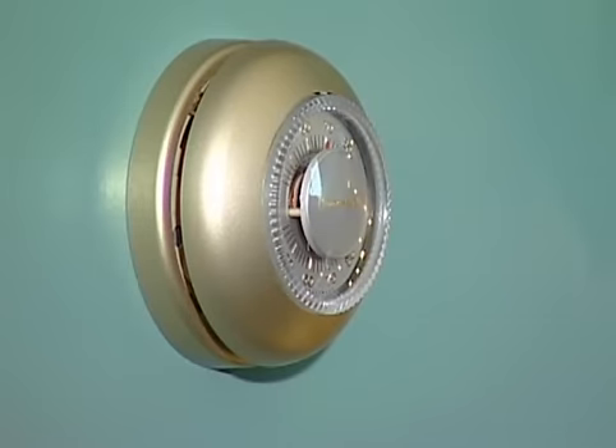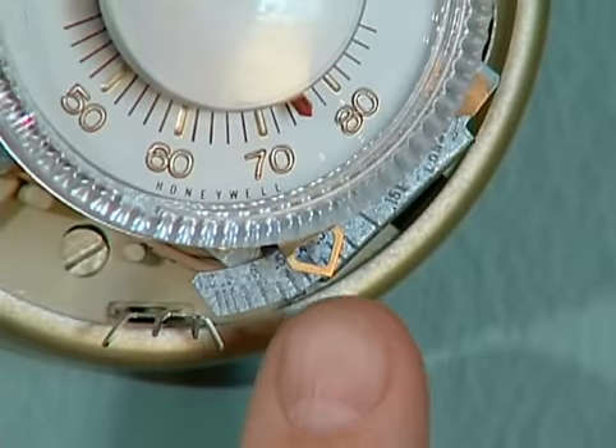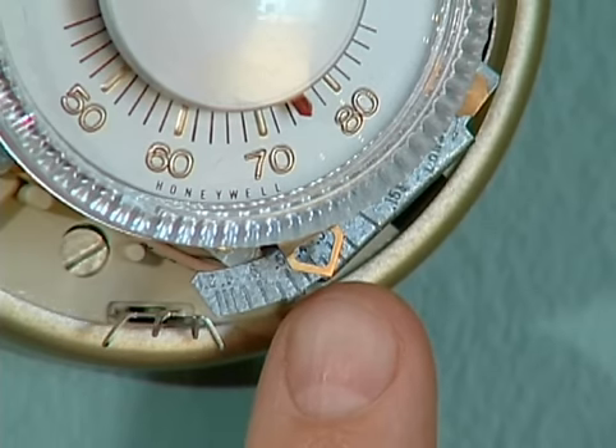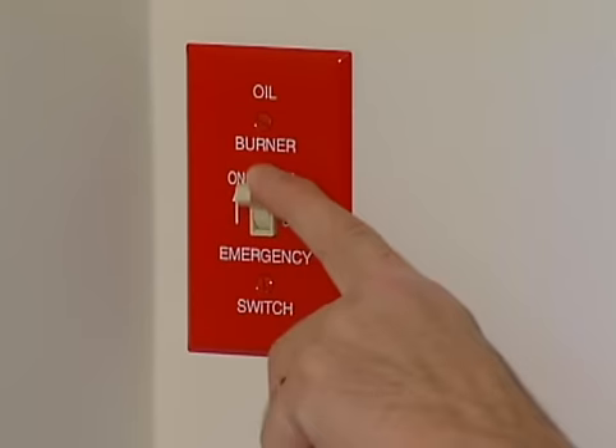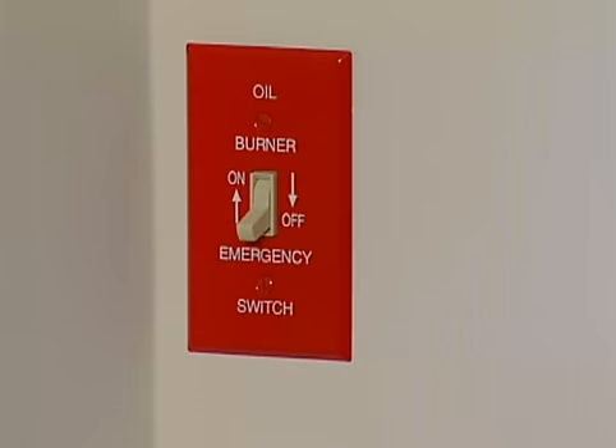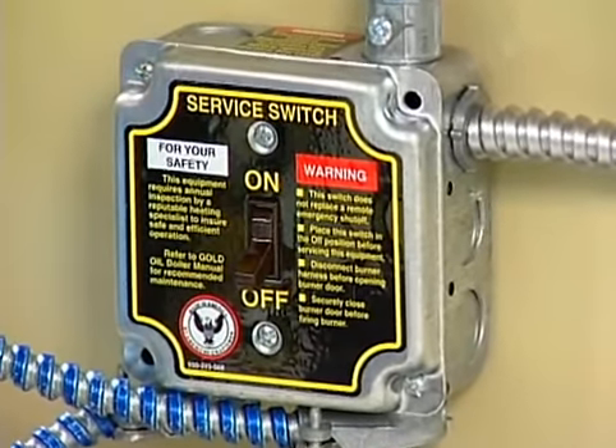Courteously interview the customer to see if they've experienced any problems with the system or if they have any questions. Listen carefully and address any concerns the customer may have. Check the thermostat before proceeding to the heating unit. Check its location, make sure it's level, and note the heat anticipator setting. Leave the thermostat calling for heat at this time. Listen to hear the burner and/or circulator, and then operate the emergency switch to ensure that it's working properly. Turn the service switch off.